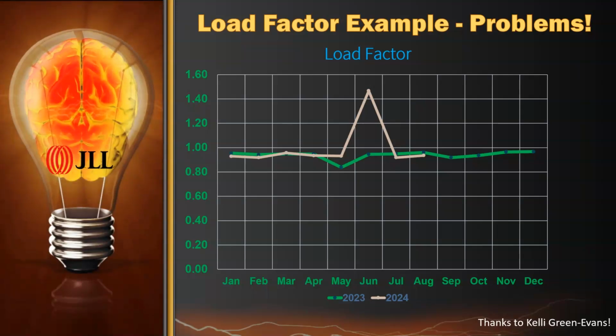But on your load factor equation, you're using kilowatt hours and kilowatts. Are both of those going to be affected, or only the kilowatt hours by putting on these chokes? That is a very, very excellent question. And I will tell you that the way power meters work is that they are very picky and very exacting about measuring each last micro piece of a kilowatt hour. That's done for a number of reasons, because when they first came out, they were pretty sloppy and they didn't do a very good job of it.